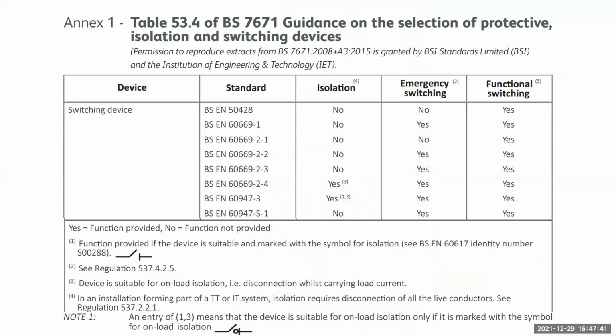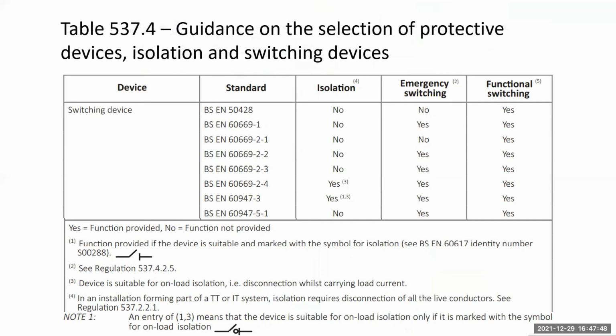The Best Practice Guide 2 Issue 3 also talks about Table 53.4, which has now changed for the 18th edition to Table 537.4, although the table remains unchanged. As we look down this table, it tells you the device, it tells you the standard, it tells you whether it's suitable for isolation, whether it's suitable for emergency switching, and whether it's suitable for functional switching. It will also tell you if the device is suitable for isolation, it'll be marked with this symbol. If the device is suitable for on-load isolation, i.e. disconnection whilst carrying load, it will also display this symbol. So you're looking for 1 and 3, a main switch 60947-3 says yes, but it should display this symbol.